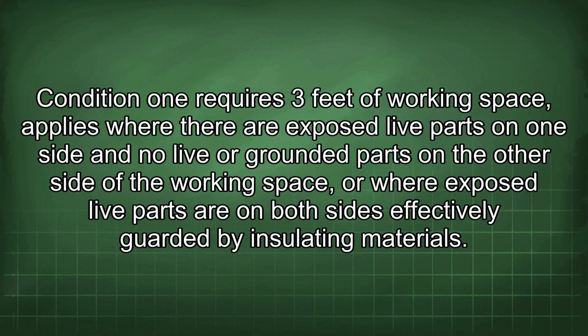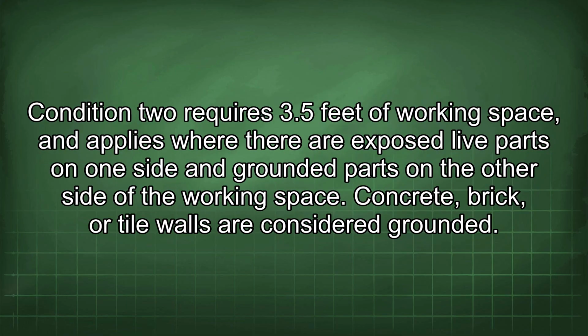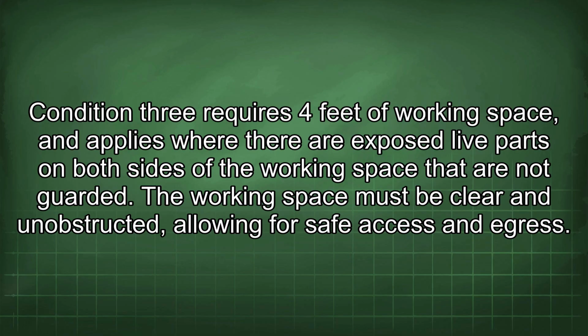equipment. Condition 1 requires 3 feet of working space, applies where there are exposed live parts on one side and no live or grounded parts on the other side of the working space, or where exposed live parts are on both sides effectively guarded by insulating materials. Condition 2 requires 3.5 feet of working space and applies where there are exposed live parts on one side and grounded parts on the other side of the working space. Concrete, brick, or tile walls are considered grounded. Condition 3 requires 4 feet of working space and applies where there are exposed live parts on both sides of the working space that are not guarded.